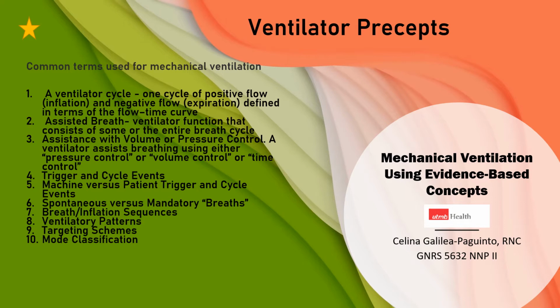Number 6. Spontaneous versus mandatory breaths. A spontaneous breath is made by the patient. It may or may not be assisted by the ventilator, and it can be both triggered and cycled by the patient. And then a mandatory breath or inflation is triggered either by the baby or by the ventilator, and it may be cycled by the ventilator or the baby.